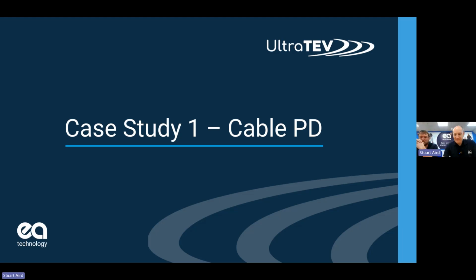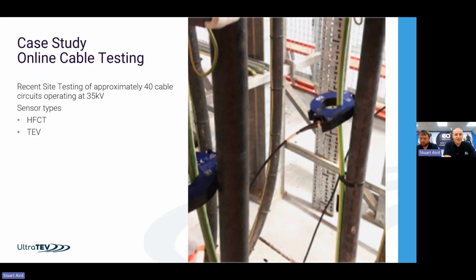Okay, thank you. So the first one we're going to go through is some cable partial discharge. We had a project where we were testing about 40 cables, all operating at 35 kV. They all had plug-in type terminations, so we could get easy access using the HFCT onto the cable earth screen at the switchgear end of the cable circuits. The customer wanted to understand the condition of these cables, and we carried out HFCT measurements and transient earth voltage measurements on each of the cable circuits.